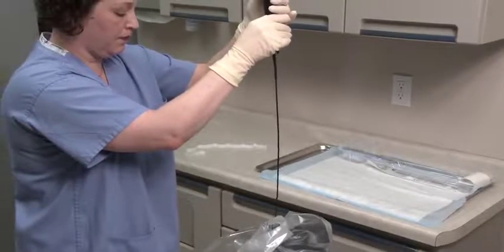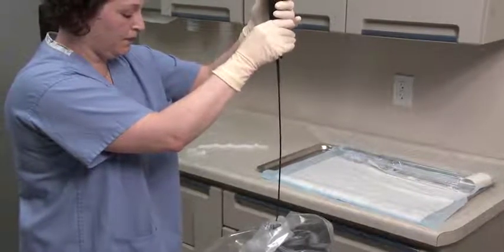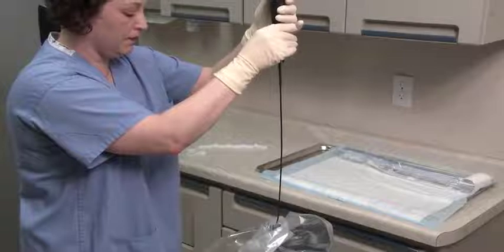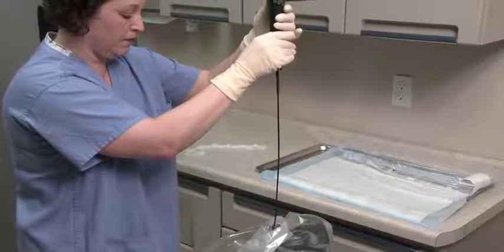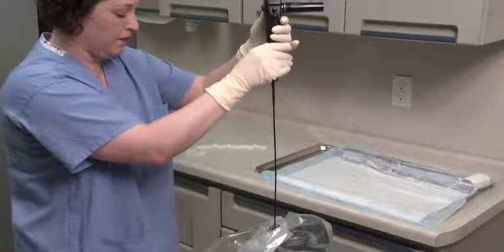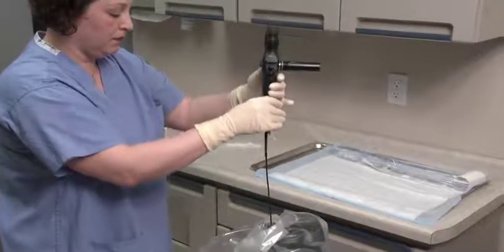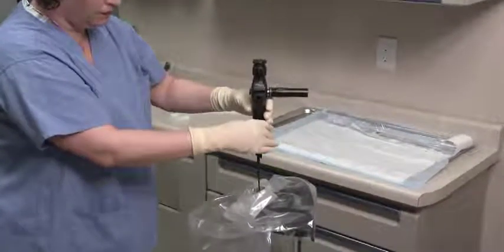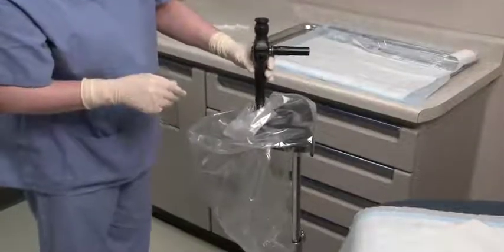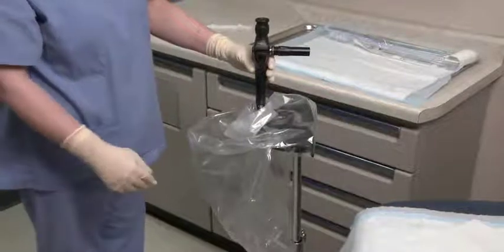While standing directly in front of the installation stand, hold the cystoscope vertically over the sheath connector. Align the scope's D-shaped insertion tube with the D-shaped opening of the sheath connector. The flat side of the scope must match up with the accessory port and tubing. Gently slide the insertion tube into the sheath. Do not twist the insertion tube during installation as it may create resistance.